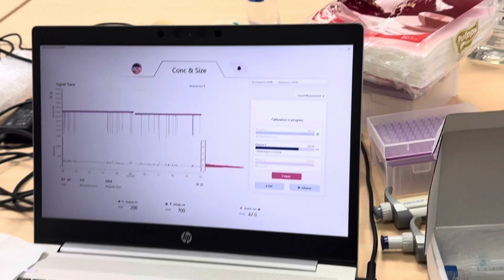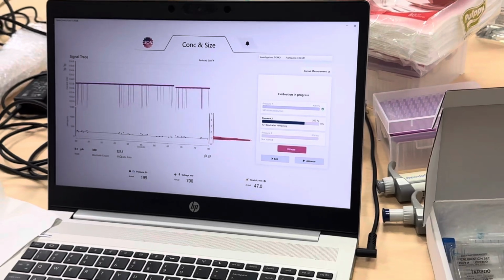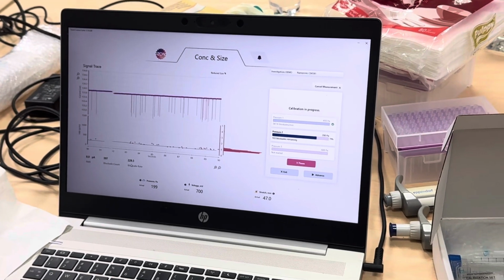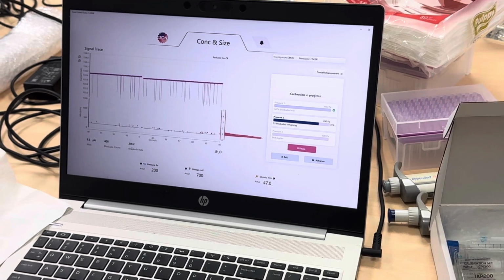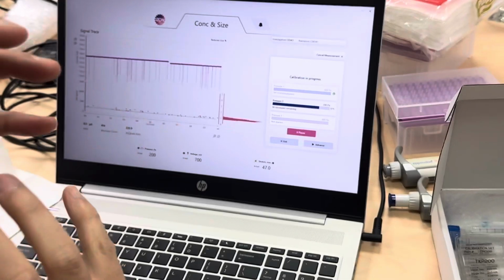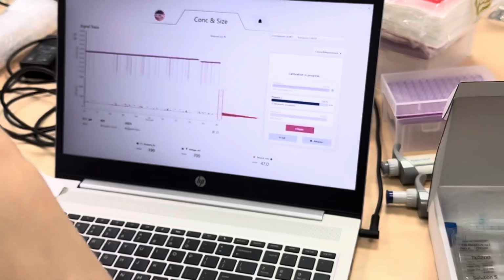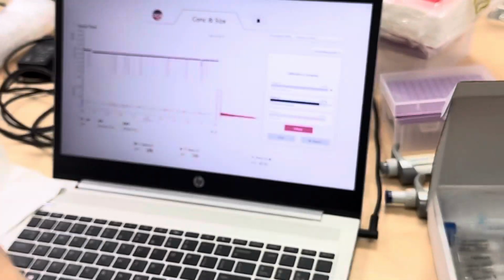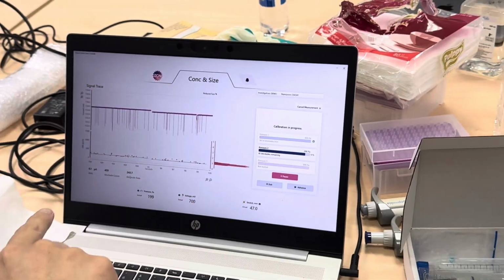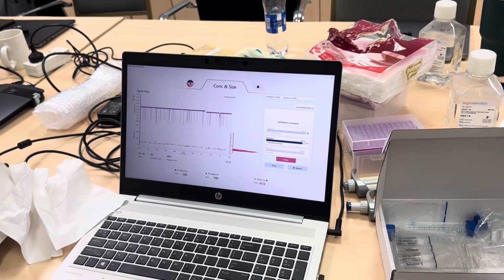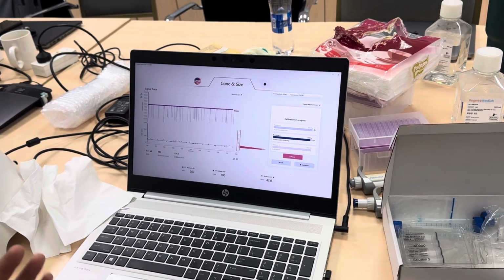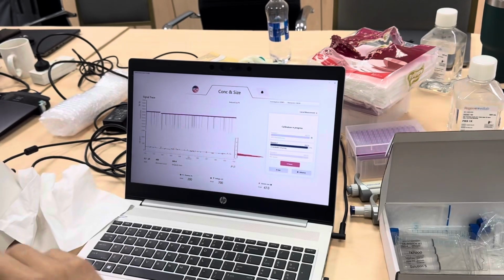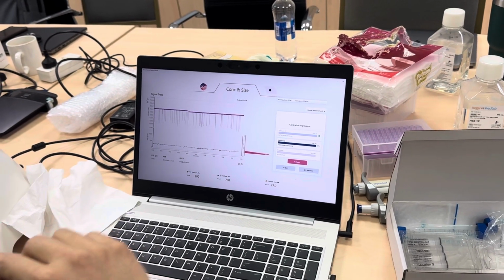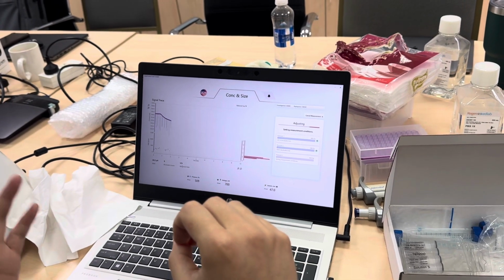Basically, the size is a little different. For the concentration, it is linear. For the size, it is to the power of 3 because it's cubic, right? So it's not linear. It's like a curve, but it's also following the mathematical formulations. So by using that way, it calculates the size and concentrations. And for the zeta potential, it's a linear shape. So we calculated the linear shape of the calibration particles and then added the things.